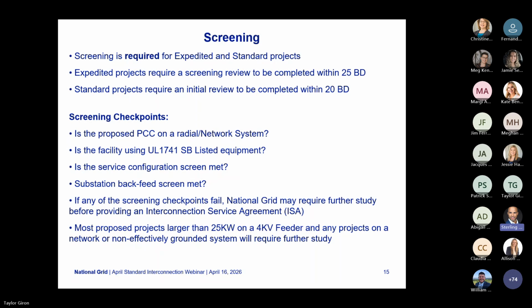Other reasons a project under 250 kW could require further study are proposed interconnection in an area with an ongoing group study, where any proposed project 25 kW or larger would be required to go through the group study process, which will be detailed a little bit later on this webinar. Most 4 kV interconnections require further study, and every proposed project on a network or non-effectively grounded system will require further study.